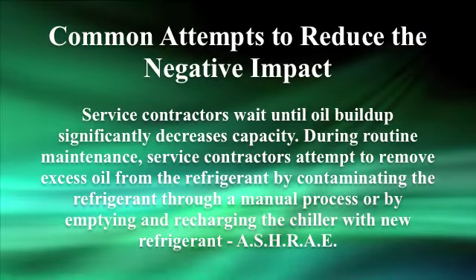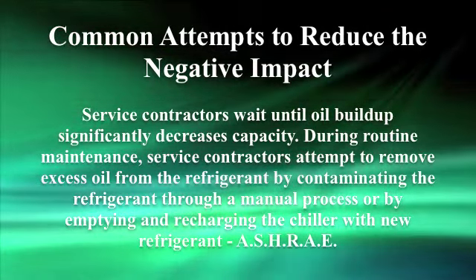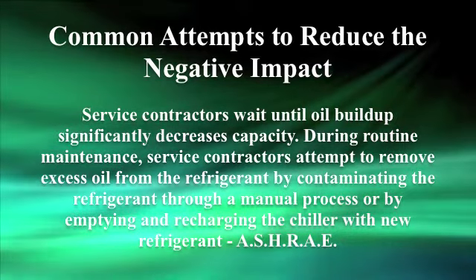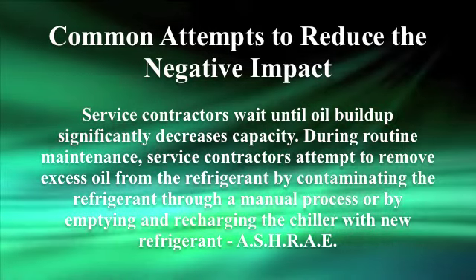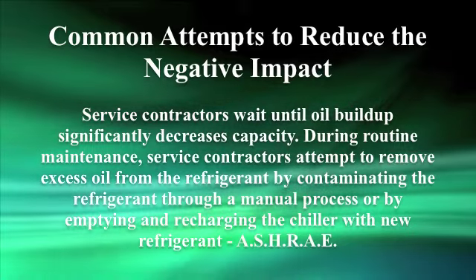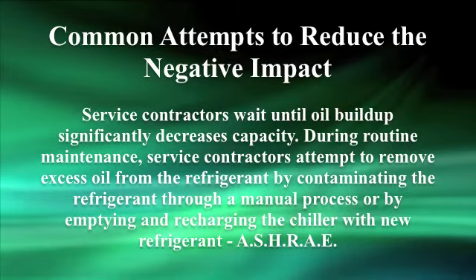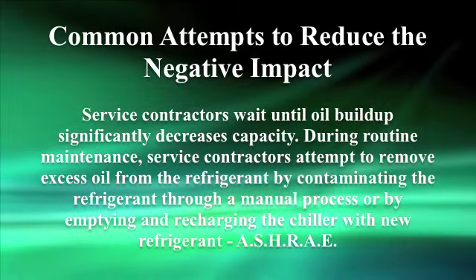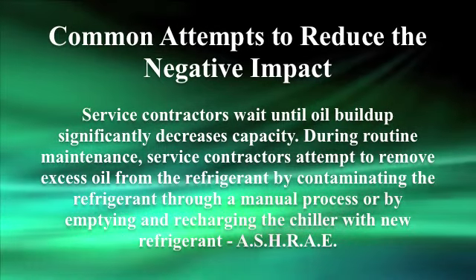Service contractors wait until oil buildup significantly decreases capacity. During routine maintenance, service contractors attempt to remove excess oil from the refrigerant by contaminating the refrigerant through a manual process or by emptying and recharging the chiller with a new refrigerant.